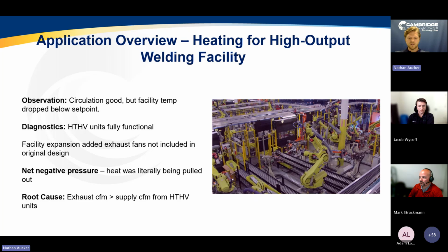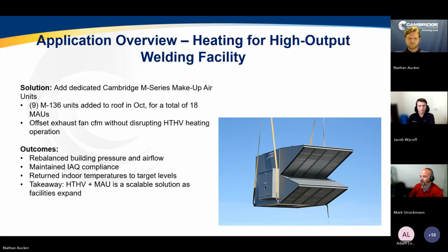And so what that equates to is some cold months in the winter, and you really need to look at the environment and what was changed within the facility when these types of things occur. And so we evaluated the equipment, learned welding stations moved from 20 to 50, and also learned exhaust was increased. And basically to bring that back into balance, we did a building study to evaluate their needs and learned quite a bit. So we added some dedicated makeup air units.